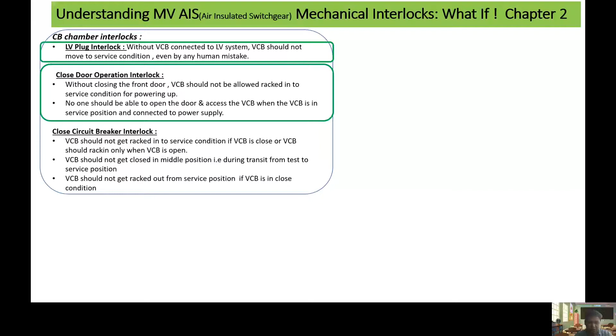So this is very easy to understand. A person should be allowed to rack in or rack out the breaker only under closed door scenario and not in open door scenario, because if a person is trying to rack in and rack out with an open door, and if there is an internal arc inside this breaker chamber, this will directly impact the person who is trying to do the rack in and rack out with open door. So let us quickly understand this with the help of this small video.